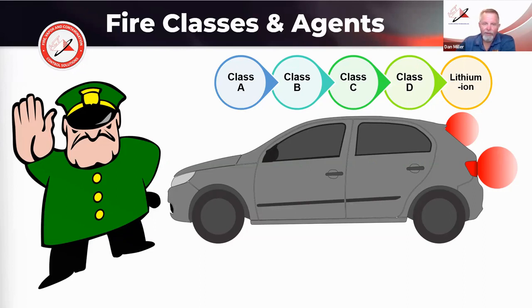Class B materials are your liquid and gaseous ignitables—any ignitable liquid or gas is a Class B. Class C is energized electrical circuits, and the biggest hazard there is becoming energized yourself, so we try to de-energize the circuit before making any fire extinguishment attempt, though that's not always possible. Class D is combustible metals, things like magnesium shavings, titanium, etc.